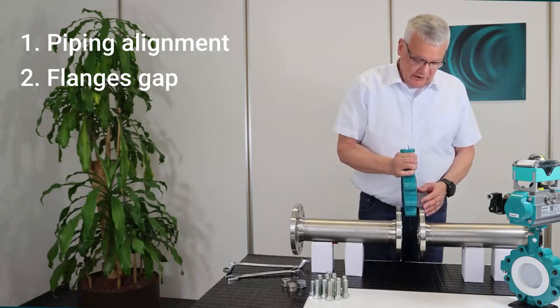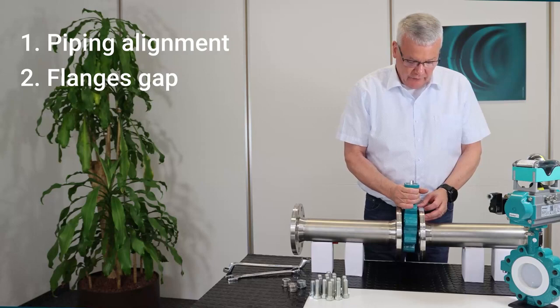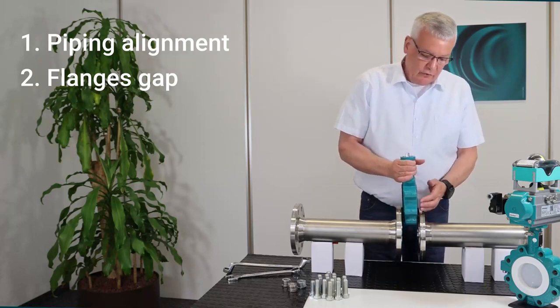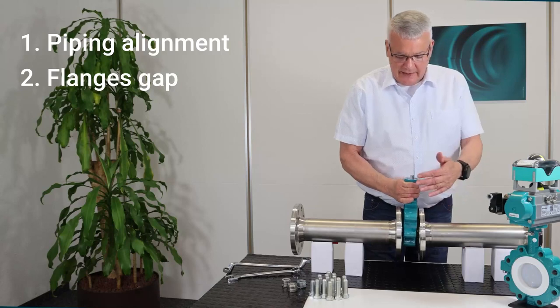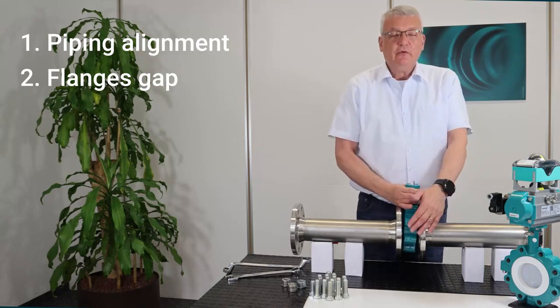Then you should ensure that the gap between the flanges is wide enough to be able to insert the valve without force, otherwise you could dislodge the liner from the body. If the gap is not wide enough, you need to use a spreader.